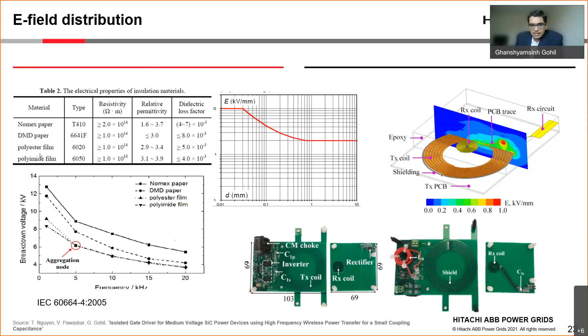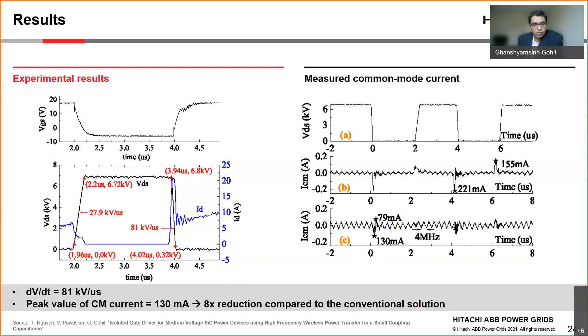These are the results - the measured common mode current, or peak value of the common mode current, without the ground shield I mentioned previously. With the ground shield, the peak value is reduced to 130 milliampere. So as I mentioned, compared to the conventional approach, this is an 8 times reduction in conducted EMI, meaning the control logic and other low voltage circuits can operate more reliably.